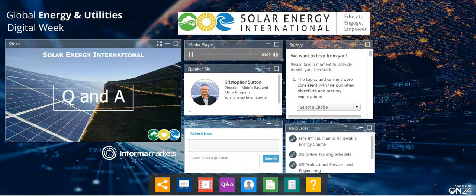Another person asked, in a situation where you're using a generator, is there any possibility of reverse power flow into the generator? Yes, there is, and not if you do it right. If we have a generator hybrid system, then we need to have a control system. In the slide I showed, there was a control module and some wires connected between them.